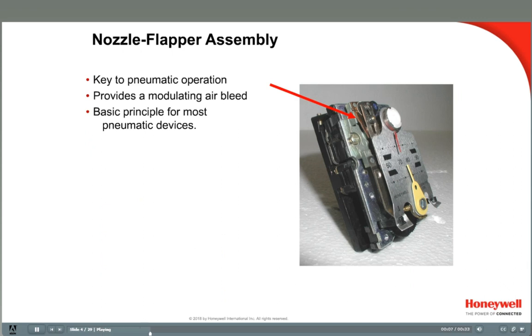The air that leaves the pressure-reducing valves is called main supply air. It goes out to each of the thermostats and controllers in the system. Inside the pneumatic controller is a simple but effective device called a nozzle flapper. It provides a way to bleed off supply air to deliver a modulated output control signal in the branch line. This air pressure in the branch line is a modulating output signal that operates valve or damper actuators or pneumatic relays.